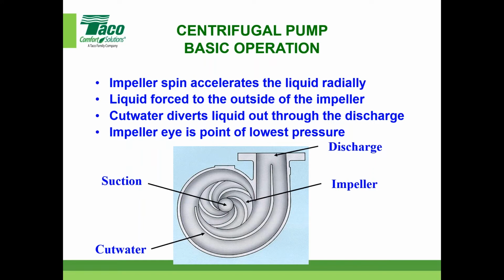There are different philosophies on that, and you could have 6 people in the room, and 3 could say one way and 3 could say another. My answer is yes, but not always. What I mean by that is it really depends on the design point and how much you have to trim it. I'm going to make up some numbers here. This impeller that's shown here could be maybe 11 inches in diameter, and the minimum size could be 8 inches. Well, if you pick a design point that's closer down to 9 inches, and you leave it full trim, when you start slowing the speed down, you just aren't going to get the savings that you expect.